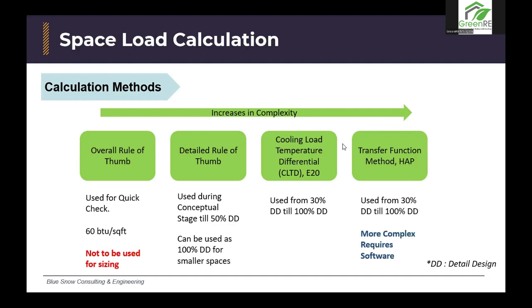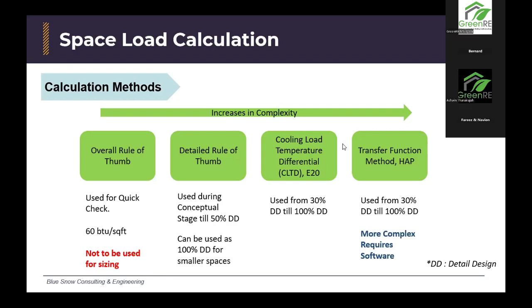The purpose of this is more to have a feel and gauge on how each space is going to play out. So normally in detailed engineering design, we have something called a conceptual stage. We have 30% detailed design, 60%, 90%, and then we have something called the IFC, which is the issue for construction stage. So that is like the 100%. So the detailed rule of thumb, again, I've seen people use this for designing semiconductor plants, which is again wrong, but it has happened. I've commissioned systems that are based on this design.